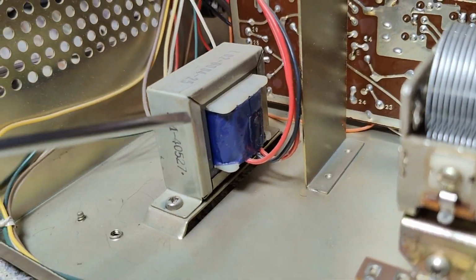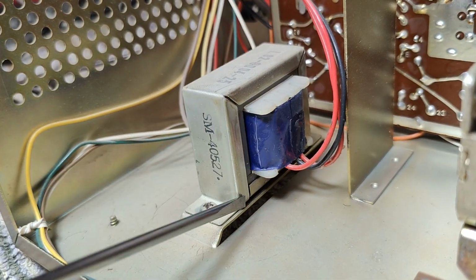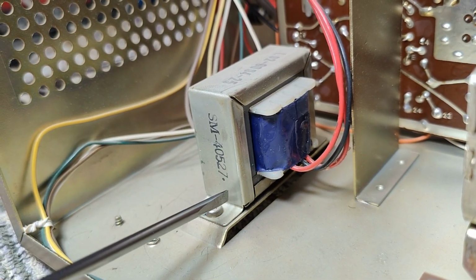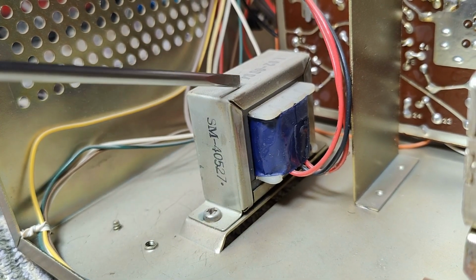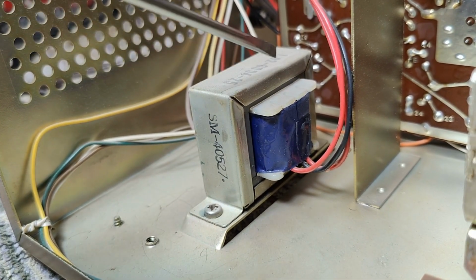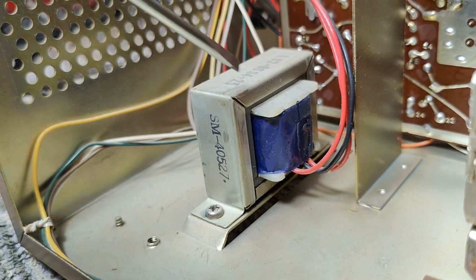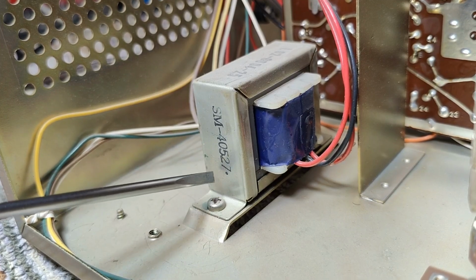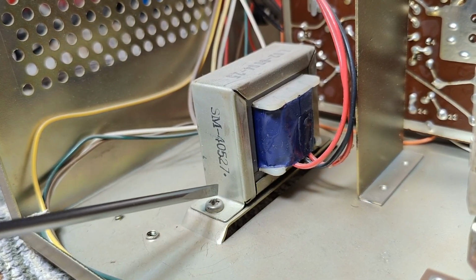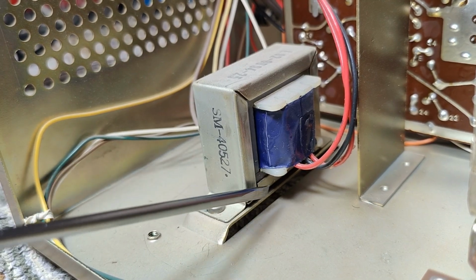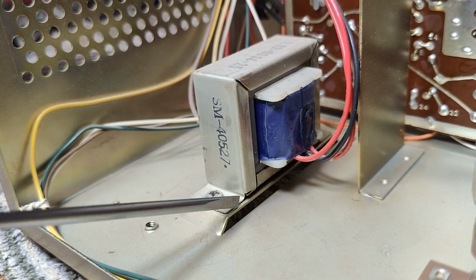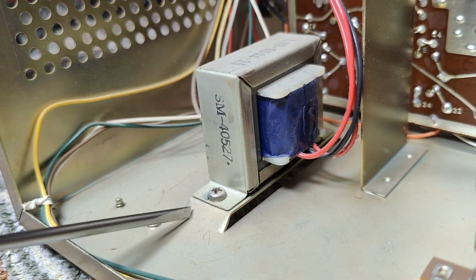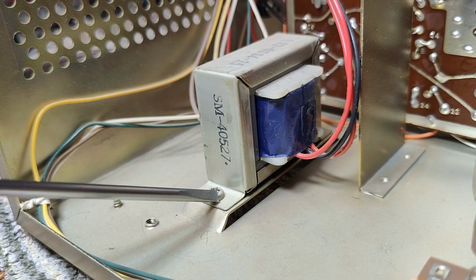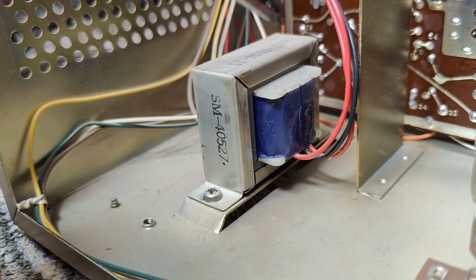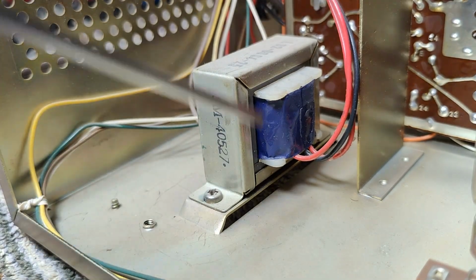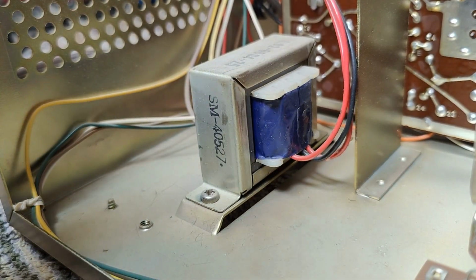But there's also another thing. If you think about it, this transformer is made of thin sheets of metal, and that's of course to break the eddy current path, because that is going around in circles like that, obviously the same way as the windings. So that is why you have all these isolated plates. But there will still be a leftover current going in the iron and the metal and the mounting and everything like that. But if you break it up like that and only have it mounted in these sides, that means you do not have currents that go between the pins or in this circular way. It's not going to transfer itself into the chassis.